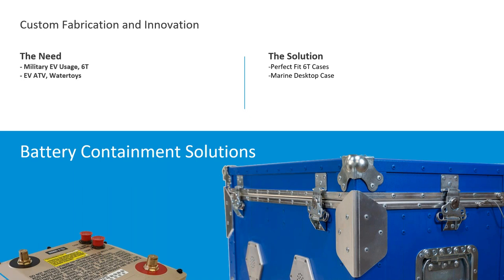We have a procedure where after every 5 domestic round trip shipments, there's an inspection procedure that you go through. You're basically making sure that the Cellblock X fabric hasn't been ripped and that it's ready to be deployed, and that there are no cracks or damage to the tiles. Very easy inspection. Very rarely is there any incident. And if there is, say they drop this thing off a truck and crack one of the tiles, you just replace the tile. It's not that big of a deal.